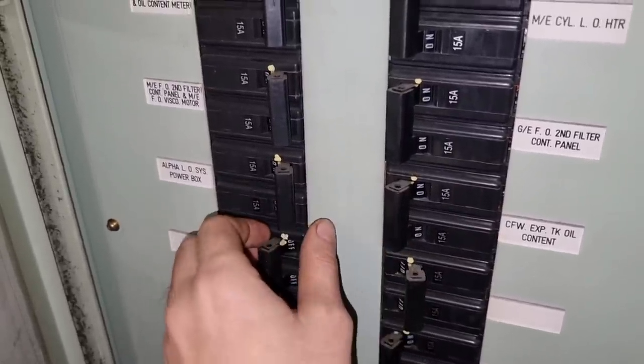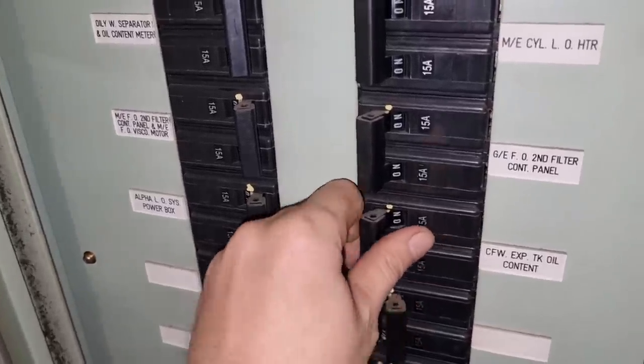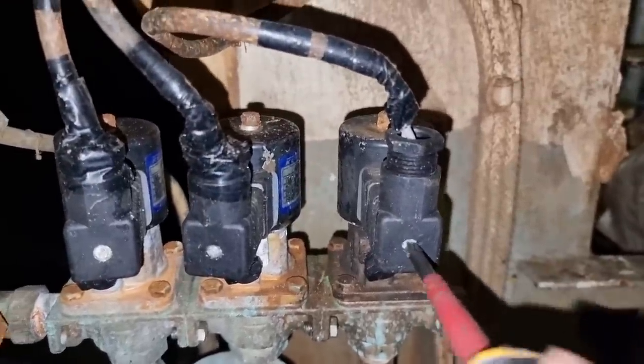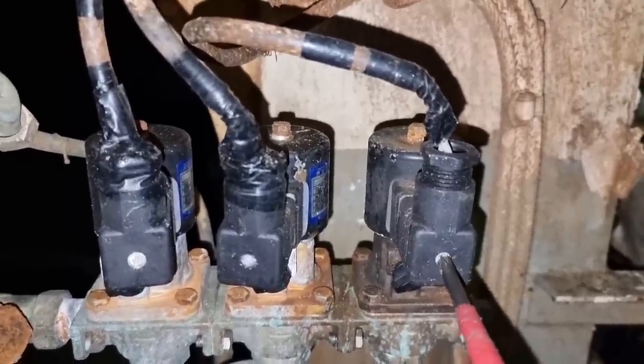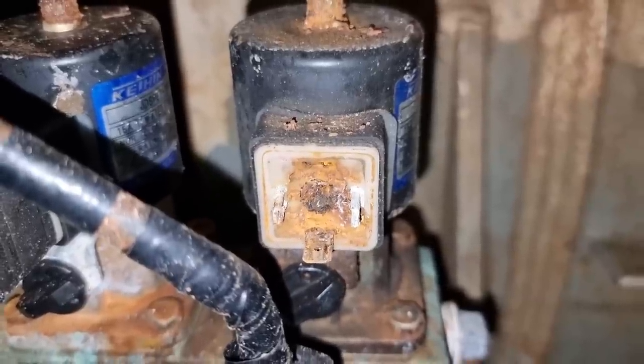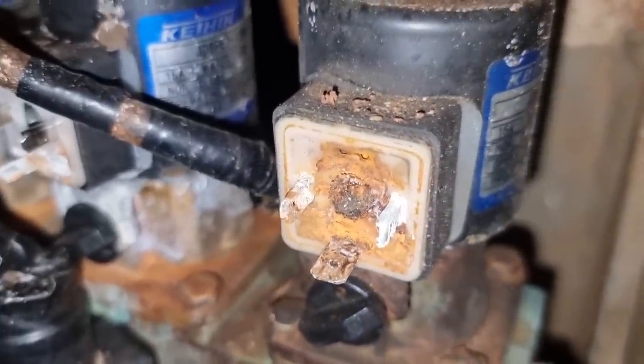The source of the fault was coming from the cargo hold lights and one of the machinery connected to the engine control console. My technique for tracing earth faults is to switch off all breakers first and switch them back on one by one to identify the culprit. I do not generally suggest tracing an earth fault in the engine control console while the main engine is running — I only did so because I reviewed the system and confirmed we had multiple power supplies. After checking everything, it turned out one of the lube oil purifiers was causing the earth fault. I noticed a solenoid coil in poor condition; after removing the wiring and checking the earth fault meter it became normal. We changed the solenoid coil, cleaned the connection, and everything went well.